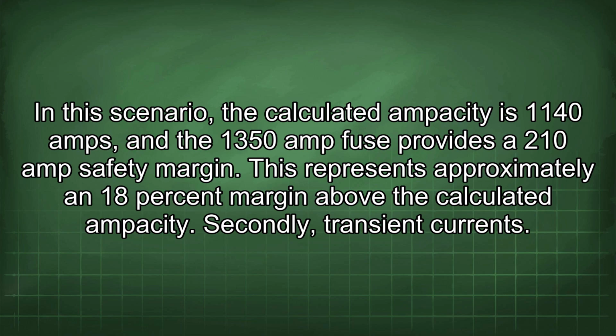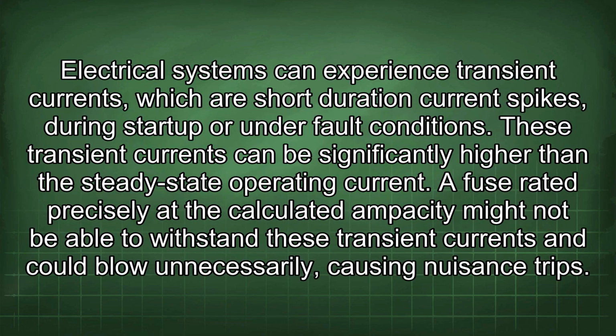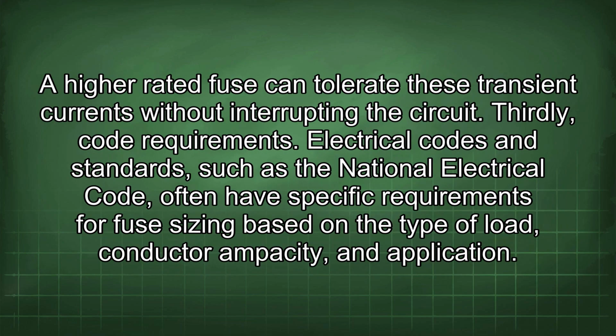Secondly, transient currents. Electrical systems can experience transient currents, which are short-duration current spikes during startup or under fault conditions. These transient currents can be significantly higher than the steady-state operating current. A fuse rated precisely at the calculated ampacity might not be able to withstand these transient currents and could blow unnecessarily, causing nuisance trips. A higher rated fuse can tolerate these transient currents without interrupting the circuit.